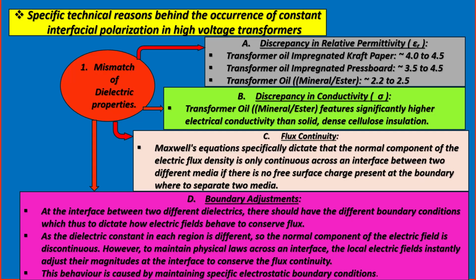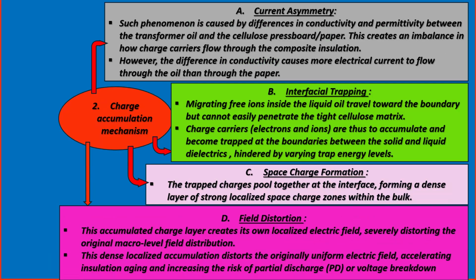This behavior is caused by maintaining specific electrostatic boundary conditions. Number two, charge accumulation mechanism. A. Current asymmetry. Such phenomenon is caused by the difference in conductivity and permittivity between the transformer oil and the cellulose pressboard and paper. This creates an imbalance in how charge carriers flow through the composite insulation. The difference in conductivity causes more electrical current to flow through the oil than through the paper.